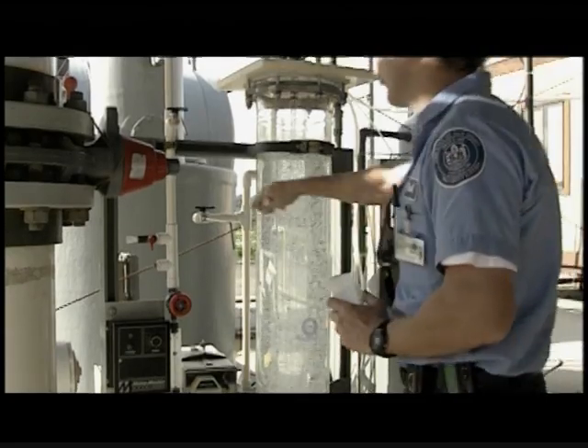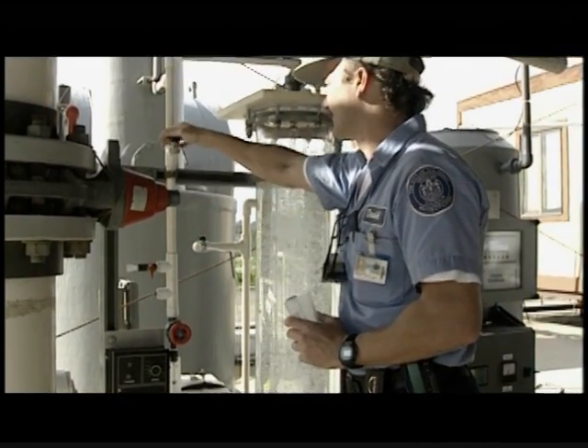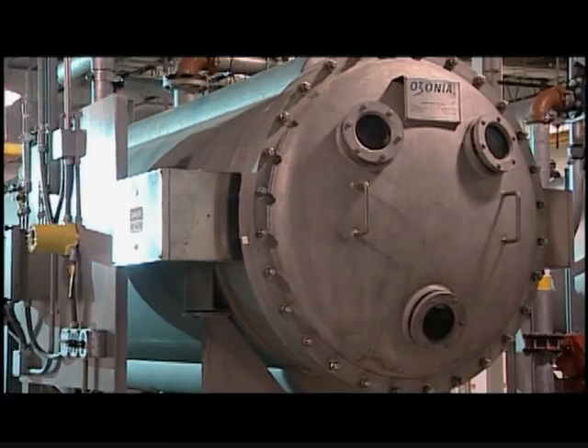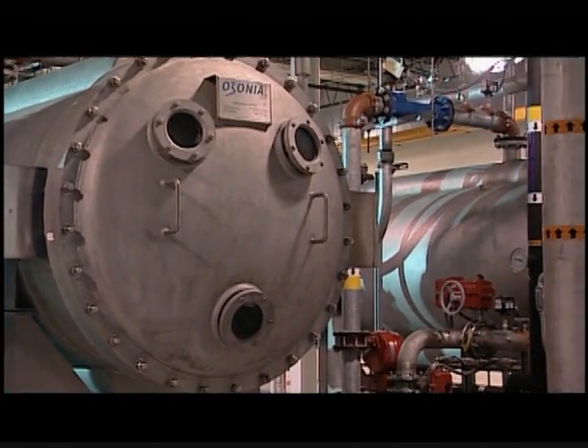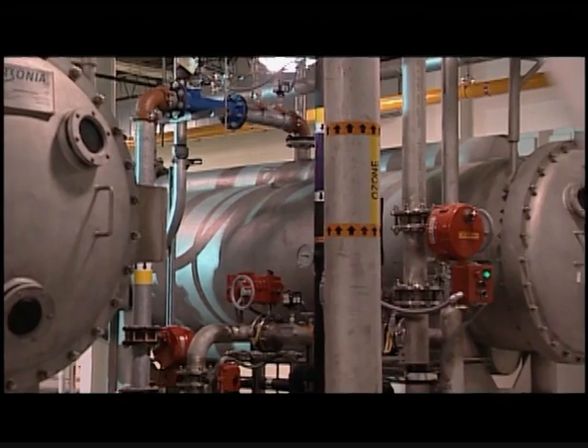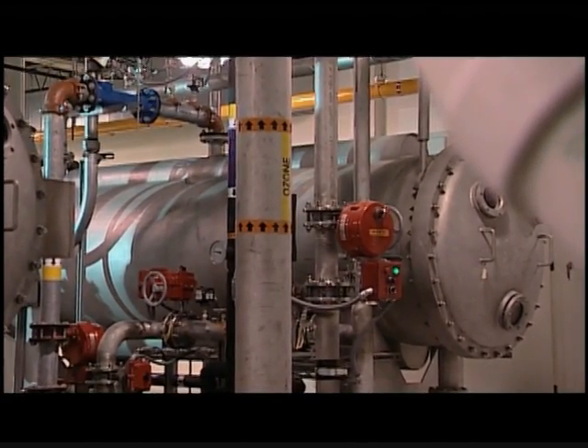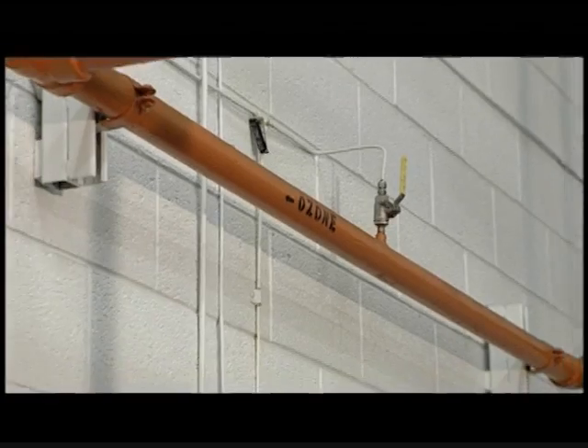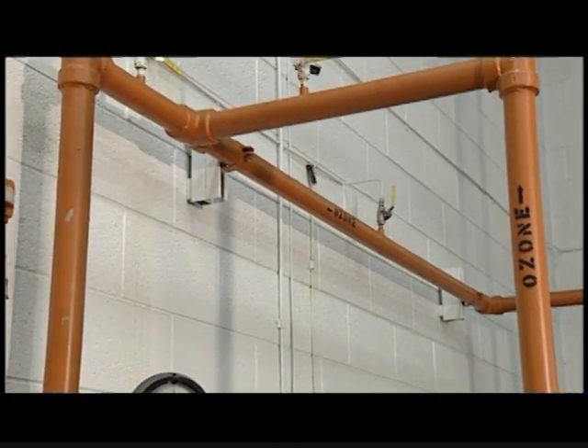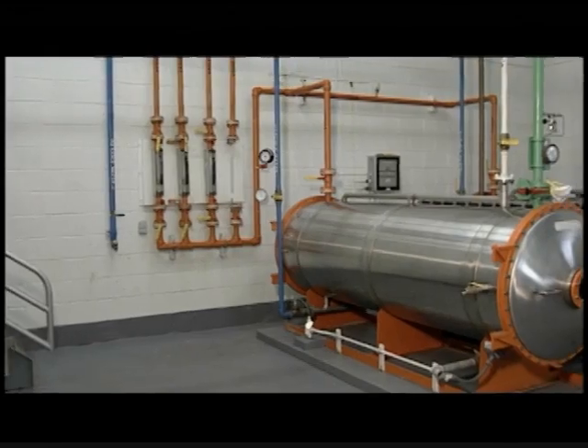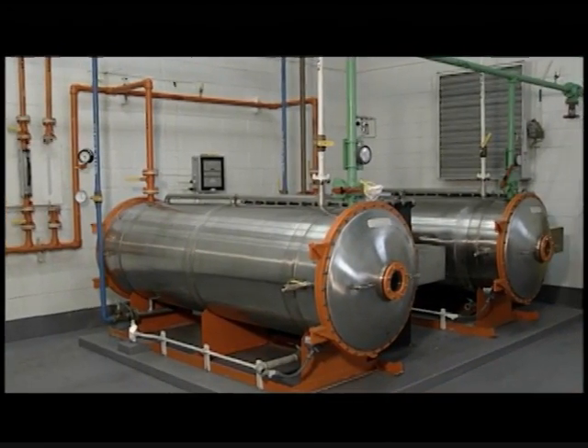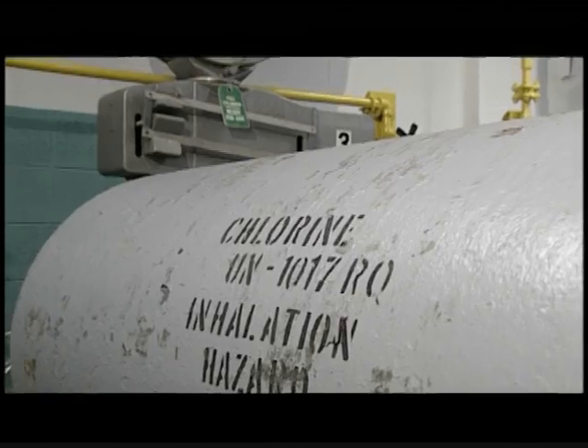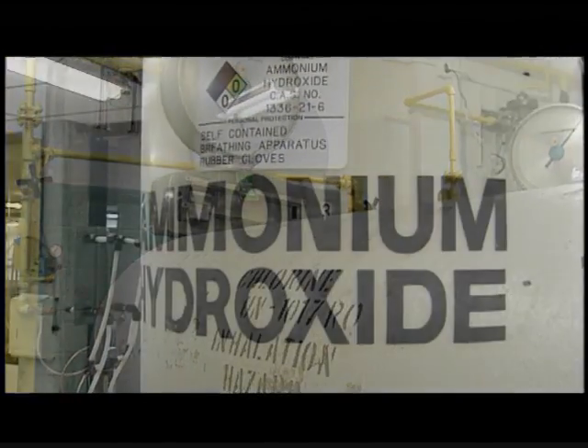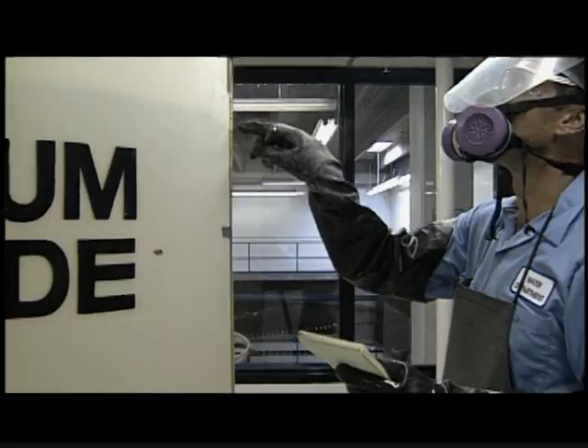Ozone is considered one of the most powerful oxidants and disinfectants available for drinking water treatment. The use of ozone gained popularity due to its effectiveness in killing and deactivating pathogens while not introducing chlorination byproducts. A powerful oxidant, ozone helps control color, taste, and odor. It is typically applied in the treatment plant at the beginning of all the processes or after sedimentation. A number of disinfectants are used for water treatment, and each has its own advantages and disadvantages. But disinfected water is essential over microbially contaminated water.